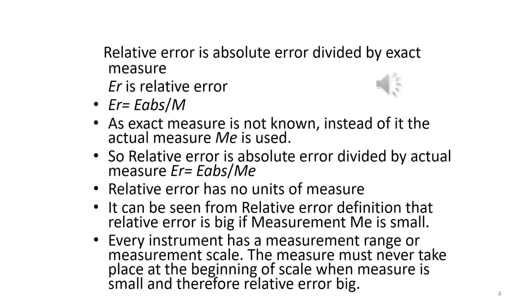Relative error is absolute error divided by exact measure. ER is relative error. ER equals E abs divided by M. As exact measure is not known, instead of it, the actual measure ME is used. So relative error is absolute error divided by actual measure. ER equals E abs divided by ME. Relative error has no units of measure. It can be seen from relative error definition that relative error is big if measurement ME is small. Every instrument has a measurement range or measurement scale. The measure must never take place at the beginning of scale when measure is small and therefore relative error big.